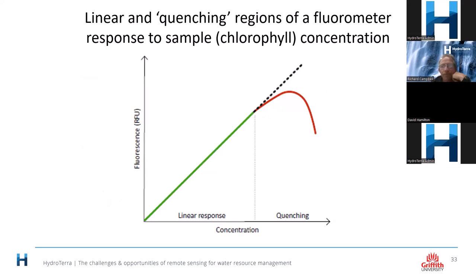The other issue is around quenching. Many of these sensors do have a quenching response. In other words, as you increase concentrations, for example of chlorophyll, you eventually reach a point where sensor responsiveness decreases. This quenching response is very important, and you have to be aware that you want to use the sensor in the linear part of its range, or else be able to readjust the range the sensor operates at.